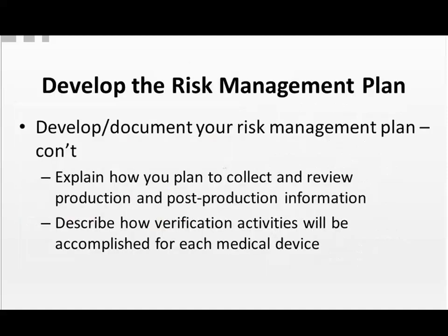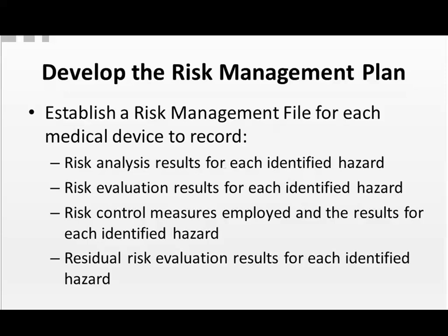And as we continue to develop our plan, you need to explain how you plan to collect and review both production and post-production information. So how are you going to collect it and how are you going to evaluate it? You need to describe how verification activities will be accomplished for each of your medical devices. Now, the plan indicates how risk management is accomplished. The repository of the data generated is the risk management file, which we briefly touched upon.